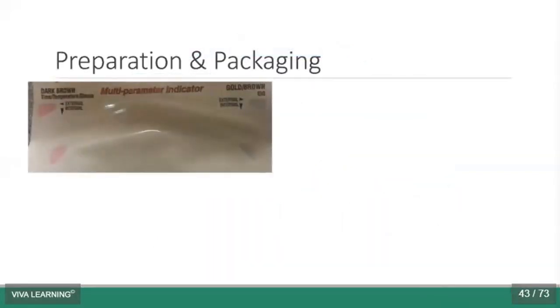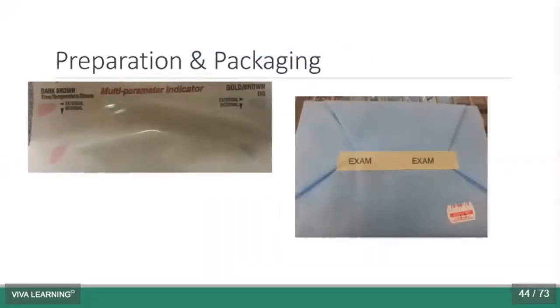Direct exposure to a contaminated item. That blue arrow shows that had you been using an automated system like an instrument washer, well, you go straight from transport to cleaning and drying. I love that the instrument washers also dry our instruments. So all we have to do is take it out, wrap it, and pop it into the sterilizer. How convenient is that? In preparation and packaging, we need to have internal and external indicators.